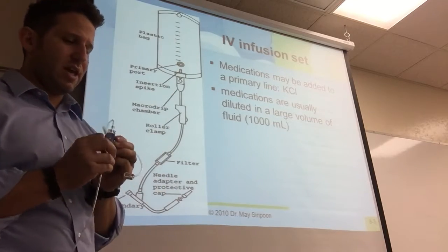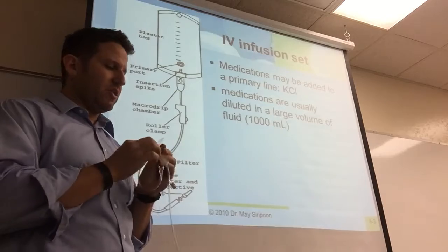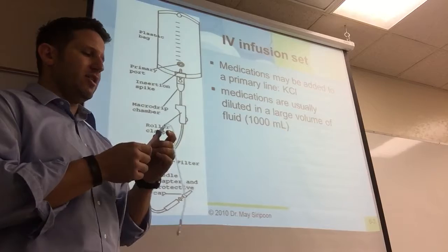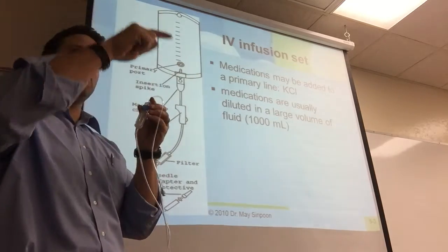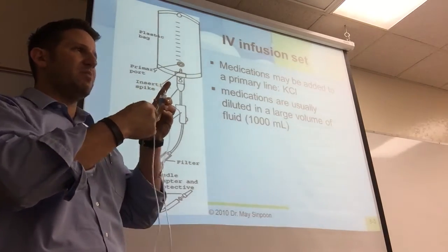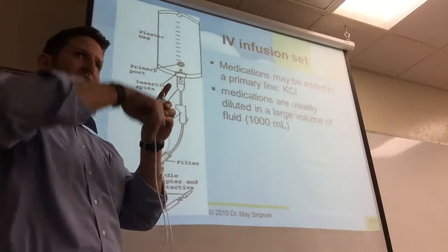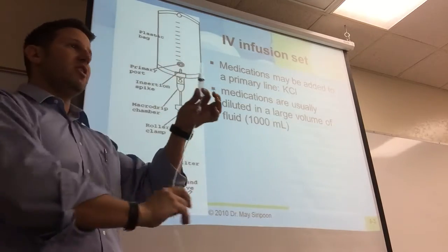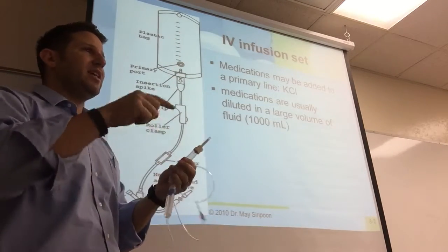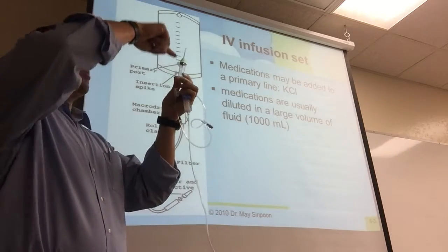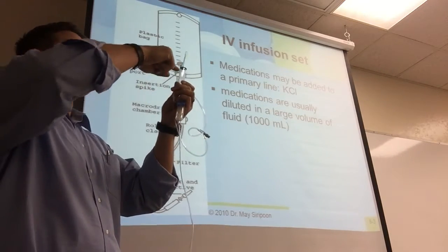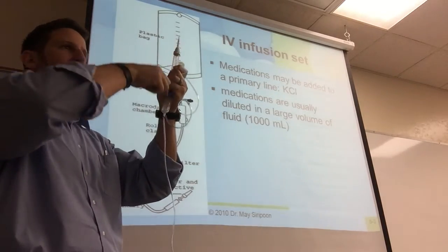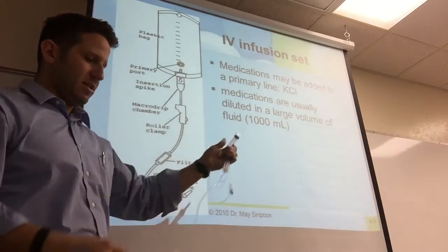This is the pump chamber. When I pass it around, you'll feel that on the back it's rubbery, okay? This clips into the pump, and there are little fingers that come up and run down the back of this in a wave-like motion, and that's what creates the force of pushing it down. So if I push down here, it's going to create suction and pull down here. So when you put it in a pump and you put it at 9999, you'll see it go drip, drip, drip, because that is the fingers going down the back and then resetting, pumping, okay? So I'll pass this around.